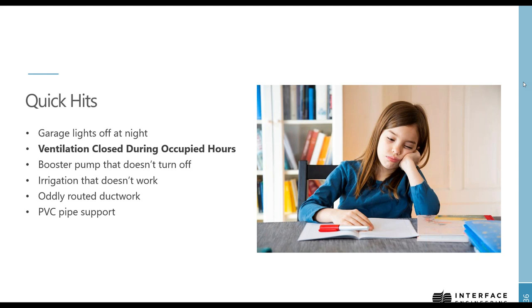Typically, this is occurring on existing buildings that have been running for quite a while. And usually it's a fix by the building engineer to solve heating and cooling issues in the building. Unfortunately, this is not the correct answer. When I find this, we open the dampers back up and then we start looking into what the real problem actually is. But it's certainly an issue that we don't want to forget about.